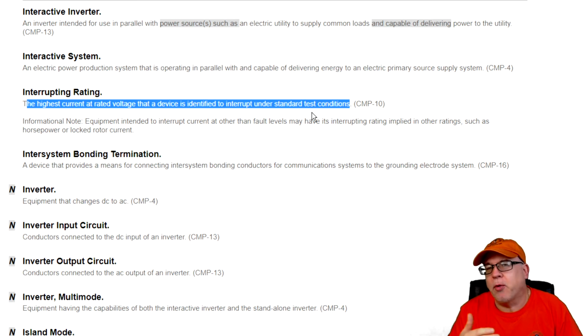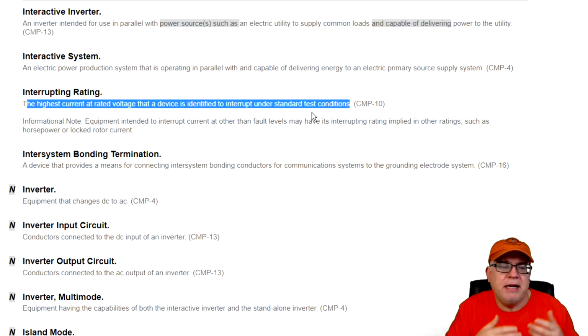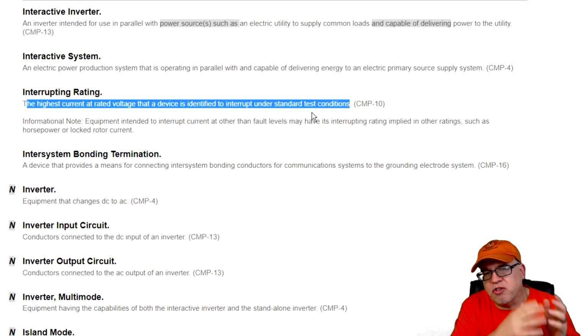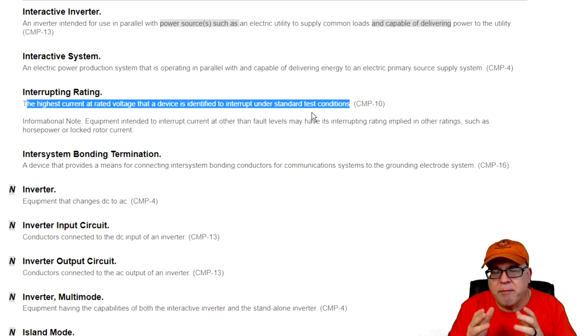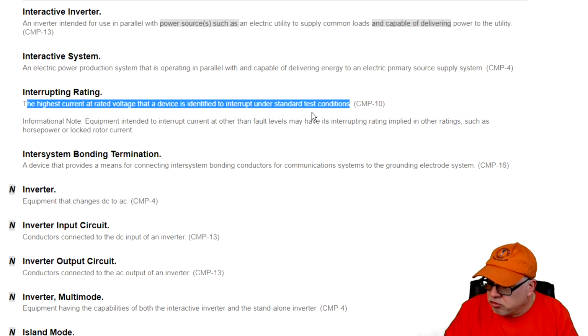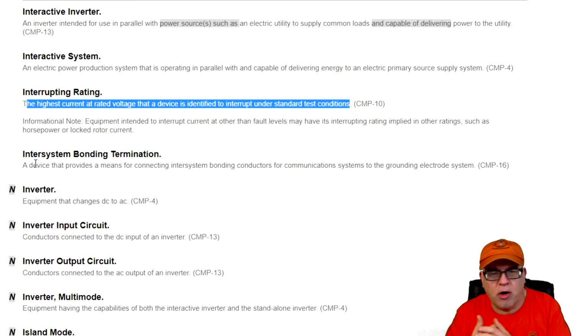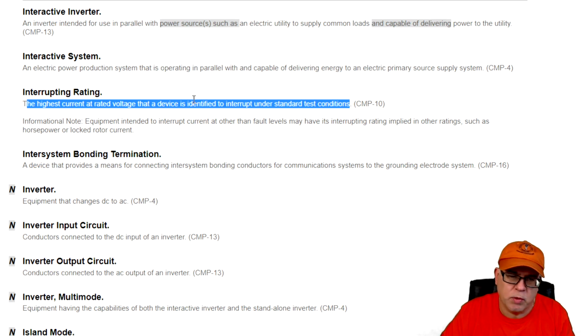So that's why it's so important for us to know what that available fault current is, okay? So main breakers, for example, if it's residential, it might have a 22,000 interrupting rating on it. So again, we need to know what the available fault current is to that equipment so that we know that breaker is not going to blow up in somebody's face when there's a short circuit somewhere. It causes that breaker to be tested, okay? So that's why we have all these available fault currents and all these things that we're trying to test for, okay?